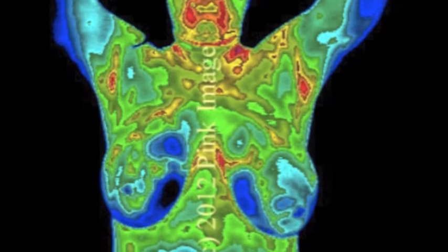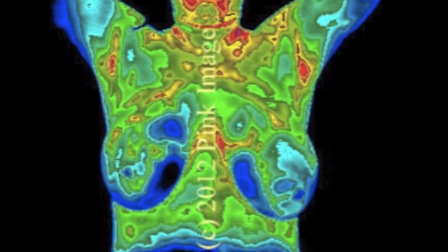As you can see in the before images, the color pattern has warm tones of red and orange. After 10 minutes of cooling down, they turn blue and green, and that's when it's imperative to take the images.